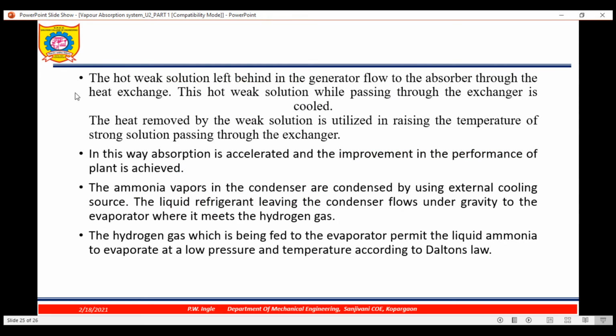The hot weak solution flows to the absorber through the heat exchanger, and while passing through the heat exchanger it is cooled because it is giving heat to the strong solution. The heat removed from the weak solution is utilized in raising the temperature of the strong solution passing through the heat exchanger. In this way, absorption is accelerated and improvement in the performance of the plant is achieved.